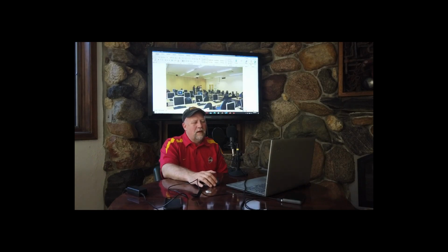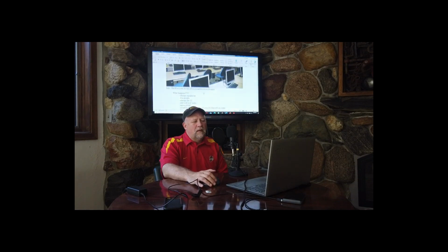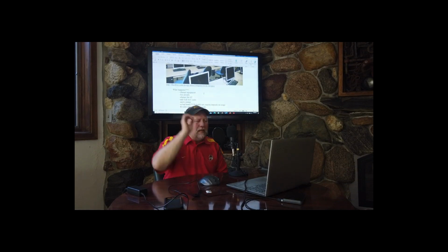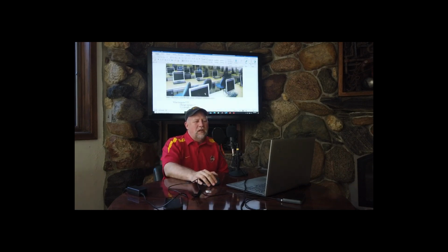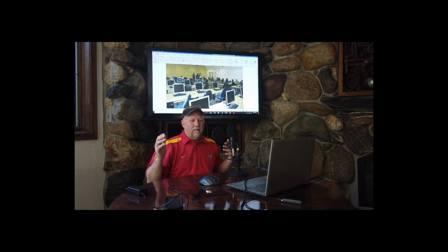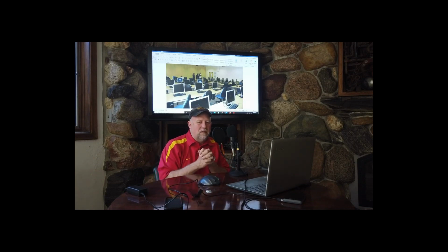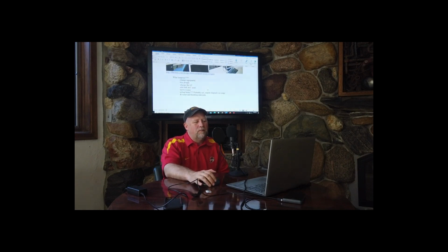All right, let's scroll on down. Here's that example. Here's a computer room. Right? Anytime that you change the occupancy or use of a room, you need to go through, or rather, you should go through this calculation to make sure that you haven't modified the room in a way that the air conditioning system can't accommodate.